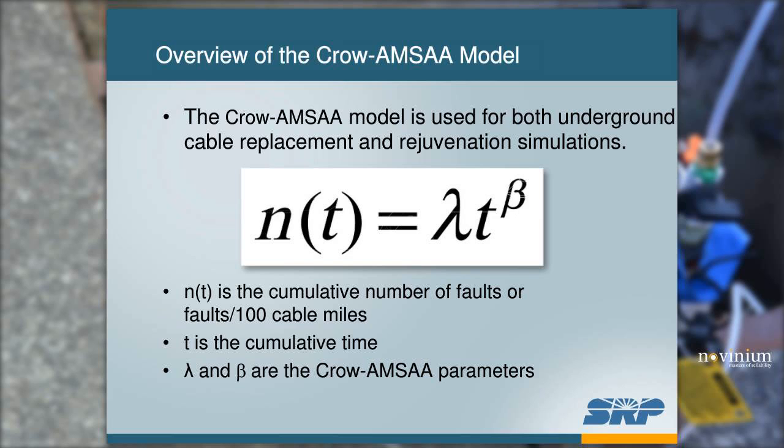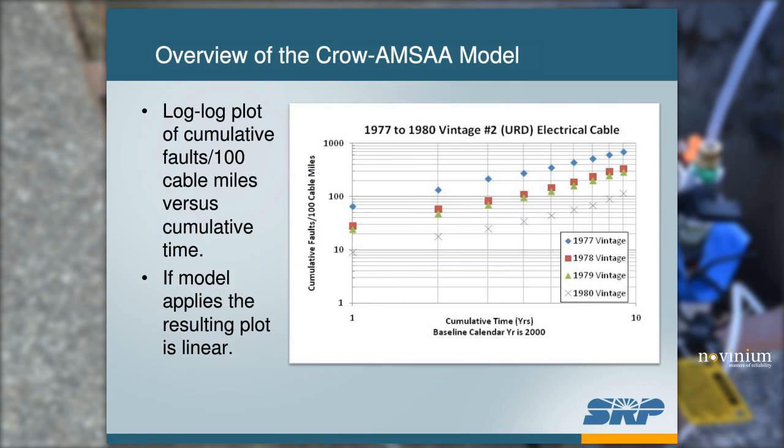The other problem that you have with the model is defining the replacement unit. I've seen several people out there want to take a continuum of cable and just arbitrarily define it as a set length of like 1 foot, 2 foot, etc., whatever the length of the splice is perhaps. Again, you cannot do that with those types of models because you're changing the distribution. So with repairable systems, a reliability growth type model, such as AMSAA, is a preferred model.